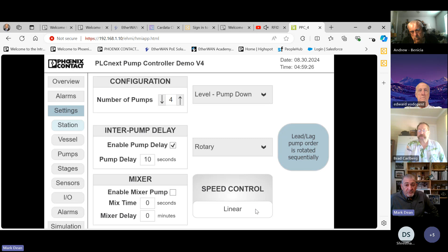In this case, we're doing a speed control that's linear, because we're using VFDs. So once you've figured out how many pumps you've got and what you're going to do with them, let's talk about what we're actually going to pump down. In this case, our shape is cylindrical, with a diameter of 10 feet and a height of 20 feet. You'll notice that gets scaled out immediately for us on the vessel right in the next window.